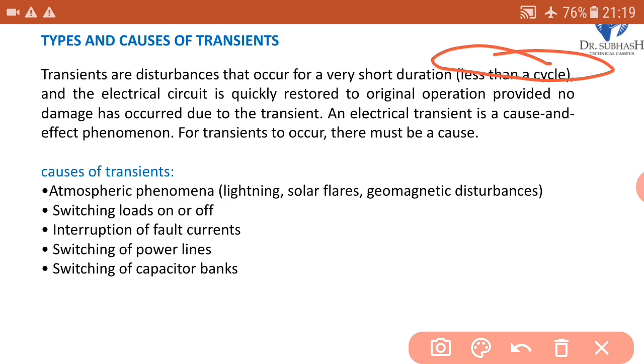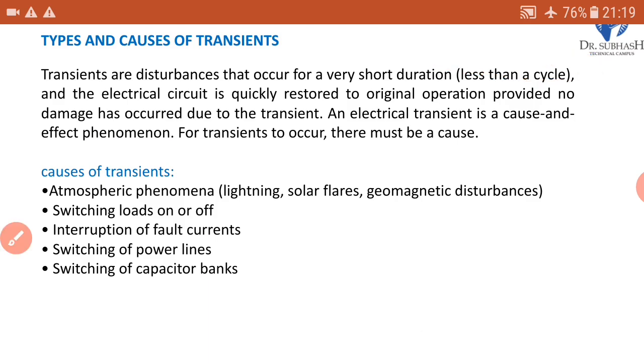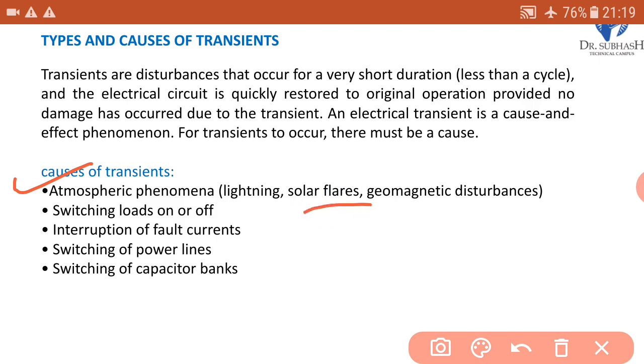An electrical transient is a cause and effect phenomenon. For a transient to occur, there must be a cause. It means a transient occurs due to some causes. So we have to see what the causes of transients are. First cause is atmospheric phenomena. Normally in major cases the atmospheric phenomenon is a lightning strike, because it is frequently seen in the monsoon or rainy season, and its effect is also very high. Some other effects are solar flares and geomagnetic disturbances, but these are rarely seen.